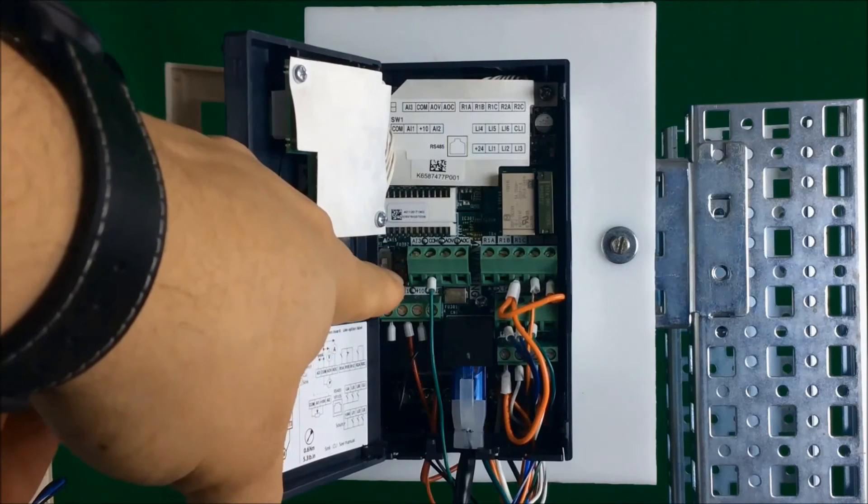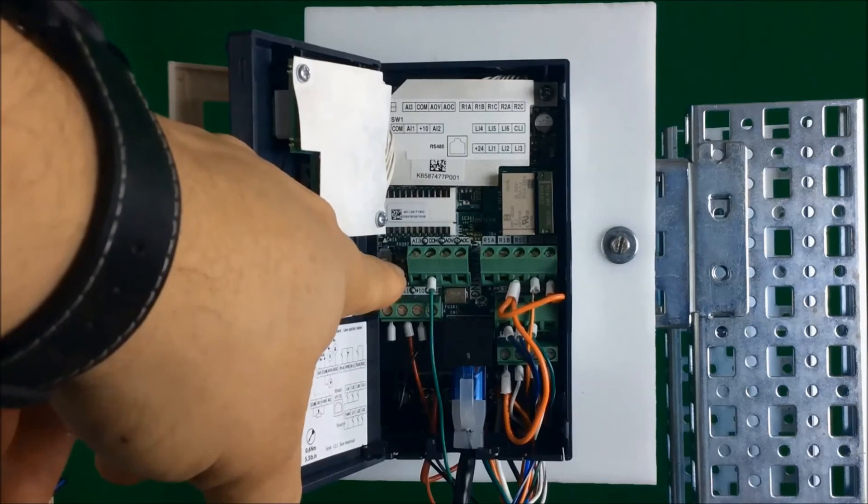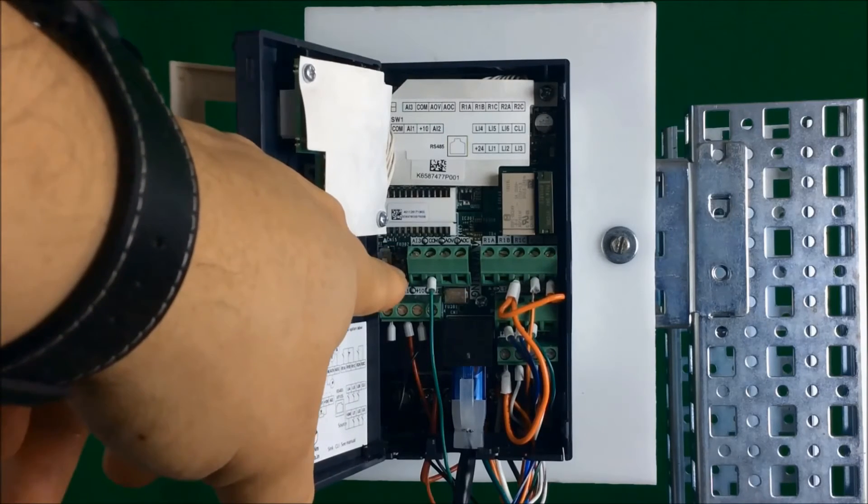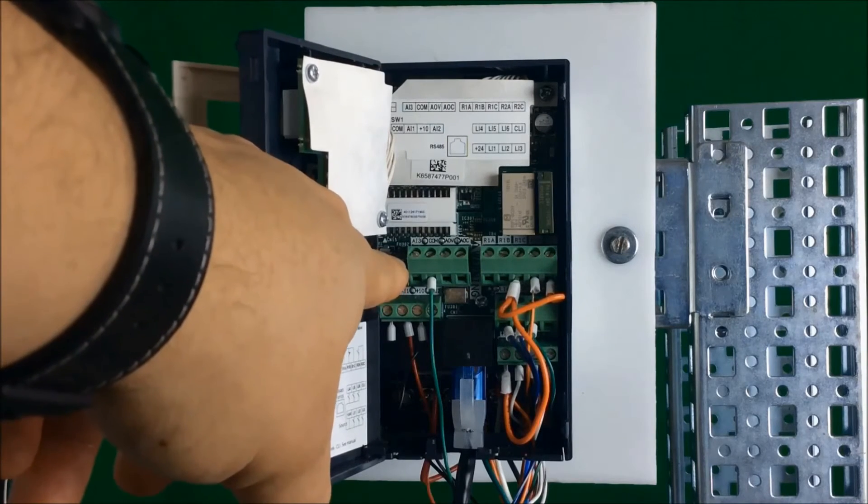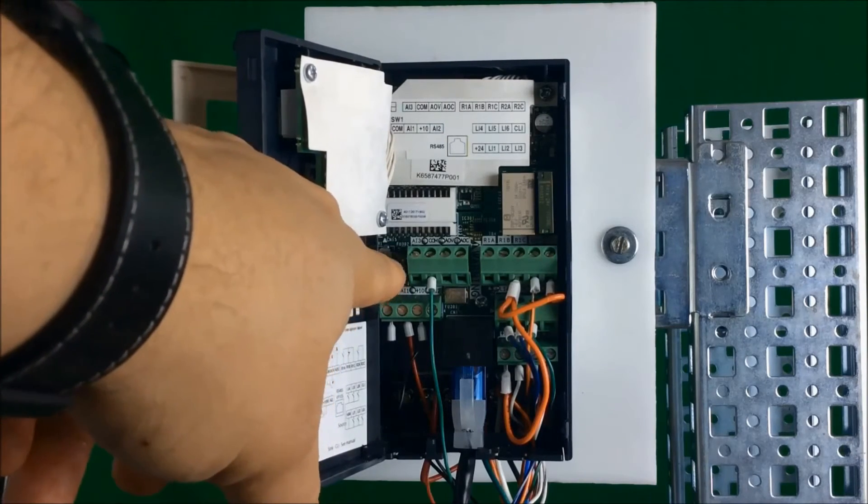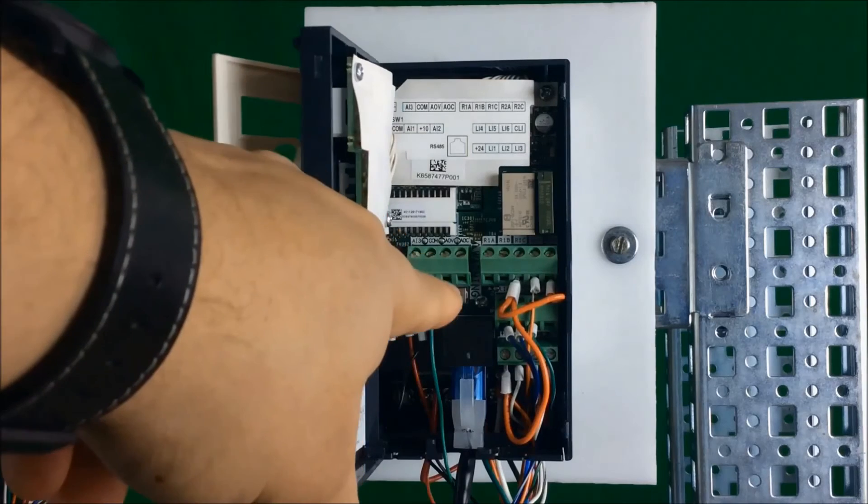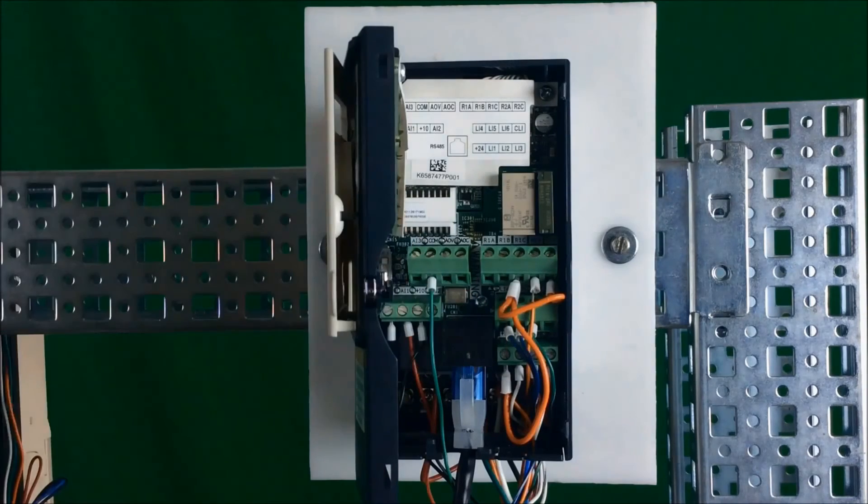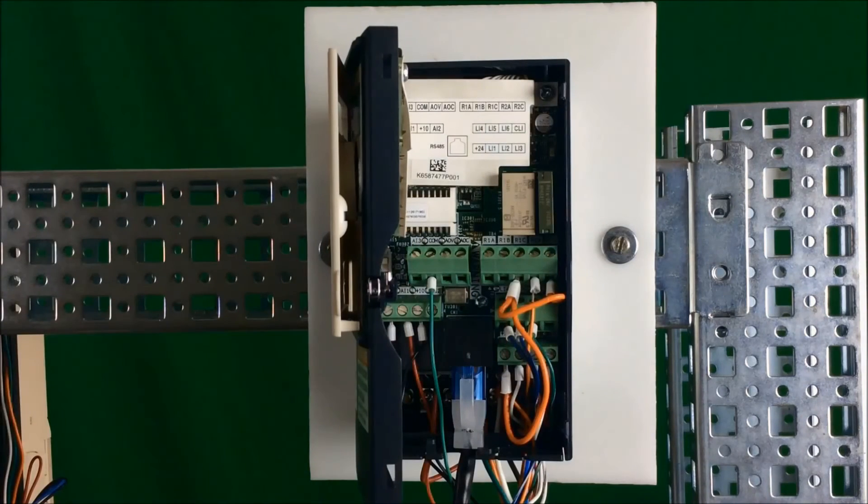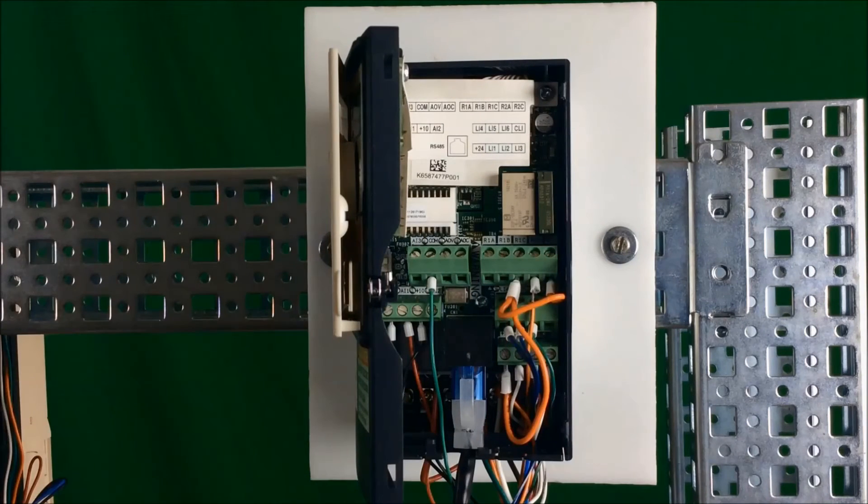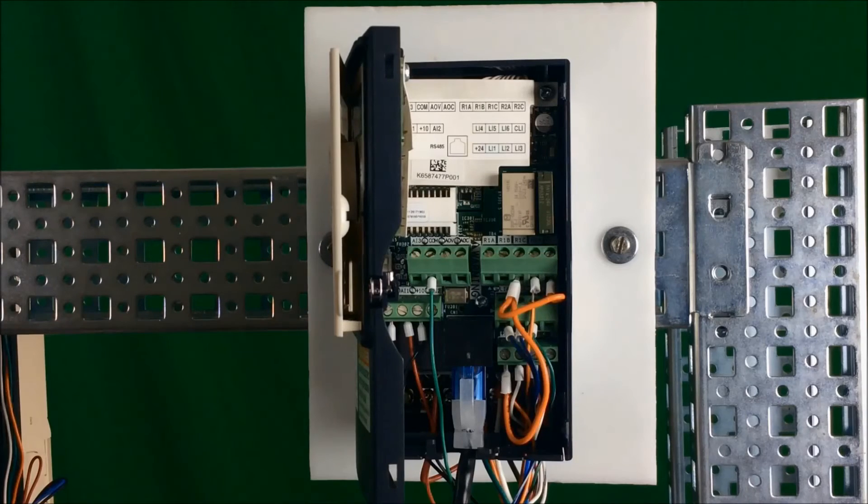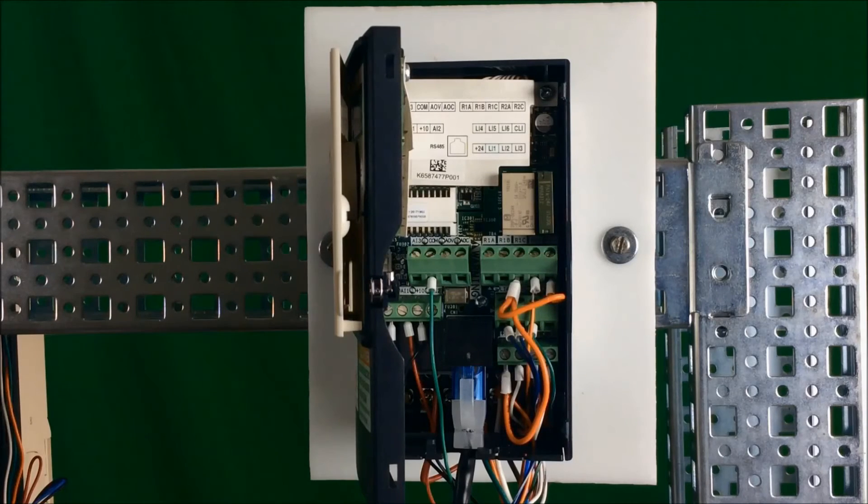If you're using a PLC to provide an input you can choose CLI. Or if you want to sink your inputs, you can turn your logic inputs on with a common input instead of a 24 volt input by setting the switch to sink.